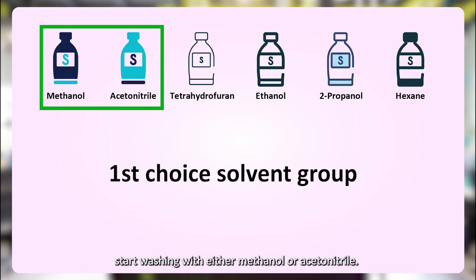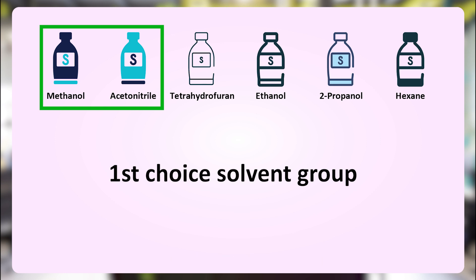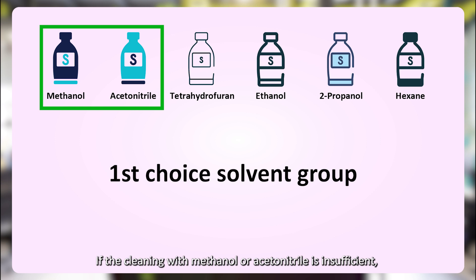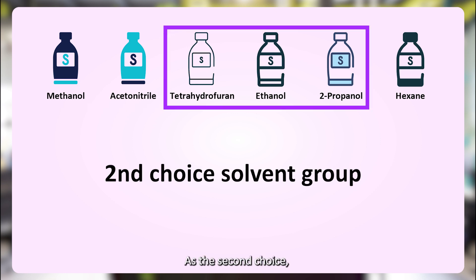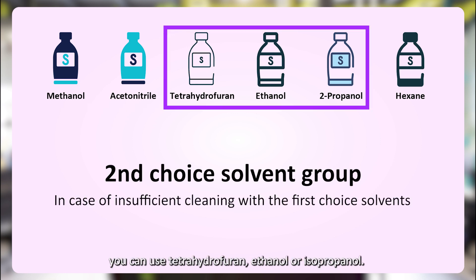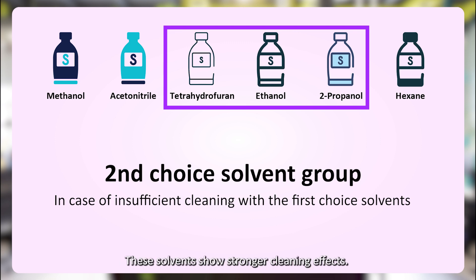We recommend starting with either methanol or acetonitrile, as they can easily be mixed with water. If the cleaning with methanol or acetonitrile is insufficient, you need to use a stronger solvent. As the second choice, you can use tetrahydrofuran, ethanol, or isopropanol. These solvents show stronger cleaning effects.